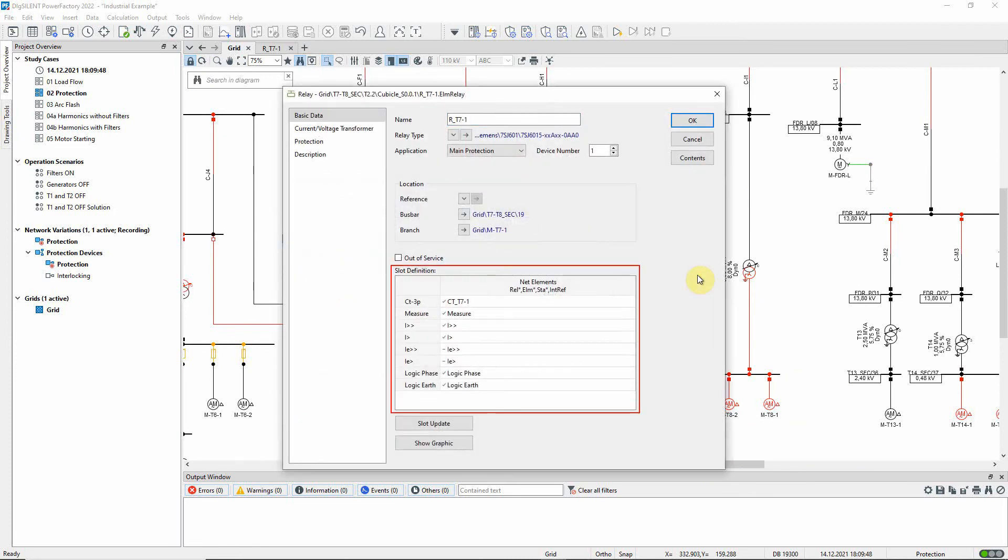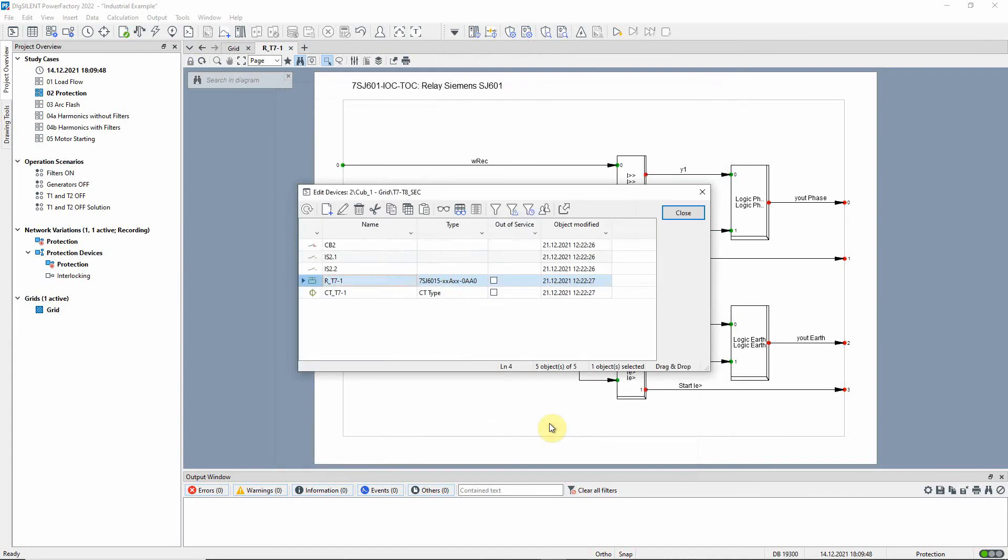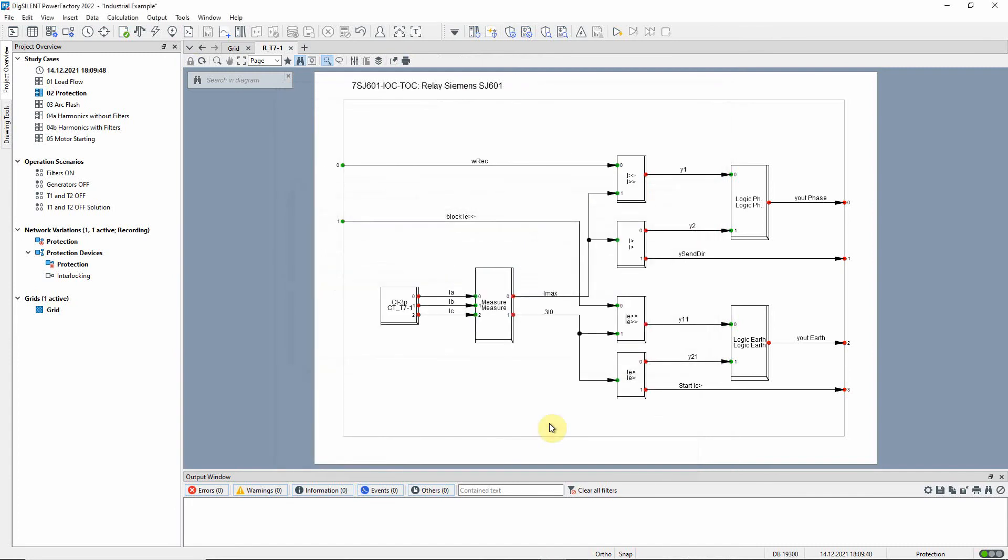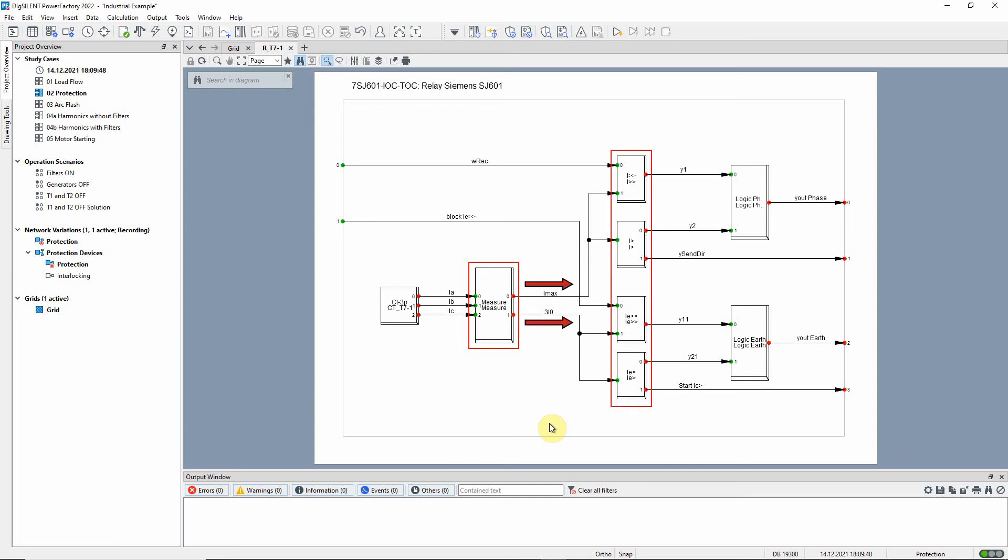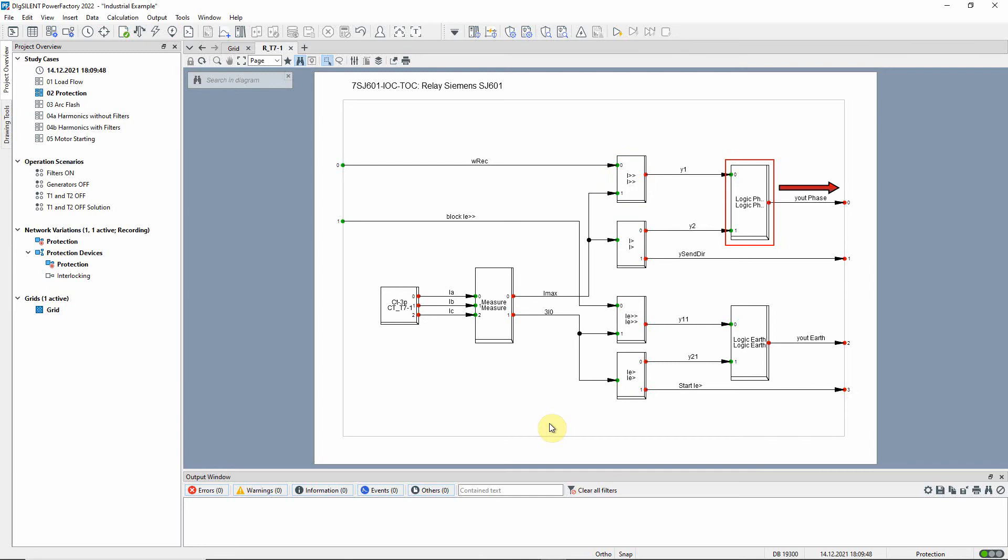Here we can see the blocks in the relay. To see how they are connected we can look at the block diagram for the relay. The current transformer measures the current and sends the information to the measurement block, which determines the maximum current value and the current for faults to ground, and sends these values to four over current blocks. If any of these sees a current that is higher than the specified pickup current, it will send this information to the logic block, which will then send a tripping signal to the circuit breaker if any of its inputs is true.